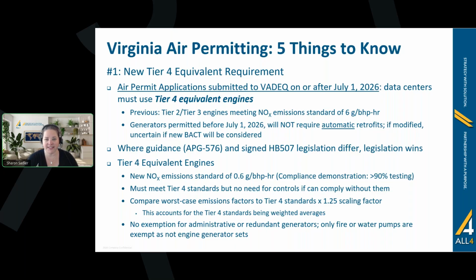When we think about NOx, which is our primary pollutant of concern in Virginia, emergency generators in those July 1st and later permit applications will need to meet 0.6 grams per horsepower hour. That's the current non-emergency presumptive BACT, as they call it, the current non-emergency short-term limit in Virginia. The expectation is that you're still going to have to do that stack testing we're all used to, at 90+% engine load. So that number is going to be in play with your permit applications.